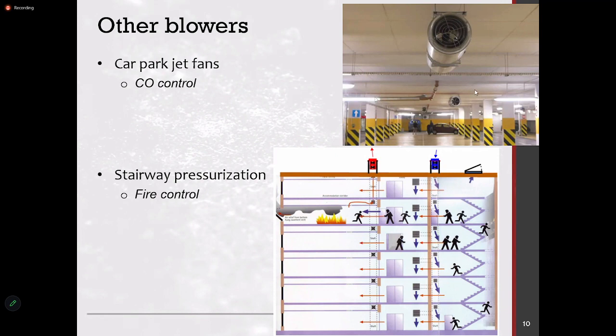Now, the key issue with buildings is when to run these jet fans, whether it should run full time or whether it should run for a certain period in time intervals, where you run for 15 minutes for every hour or so. So it is very difficult to actually judge when to run the jet fans. So ideally, what we recommend is, if possible, to do carbon monoxide monitoring, and then you switch on the fan. So similarly, even for fresh air supply.